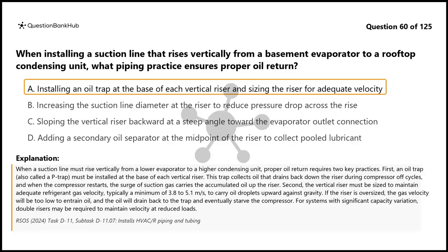Second, the vertical riser must be sized to maintain adequate refrigerant gas velocity, typically a minimum of 3.8 to 5.1 meters per second, to carry oil droplets upward against gravity. If the riser is oversized, the gas velocity will be too low to entrain oil, and the oil will drain back to the trap and eventually starve the compressor. For systems with significant capacity variation, double risers may be required to maintain velocity at reduced loads.